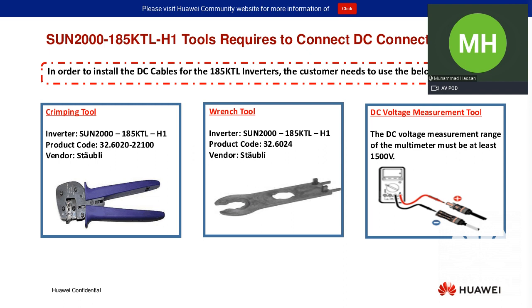Recently, I believe last week, I received a request from a customer who didn't do the DC polarity test, and they connected the strings to the inverter, and when they switched on the inverter, the DC connectors burnt out. So I always recommend that customers do the polarity test before installing or crimping the DC connectors, to make sure that everything is okay when you turn on the inverters for production.